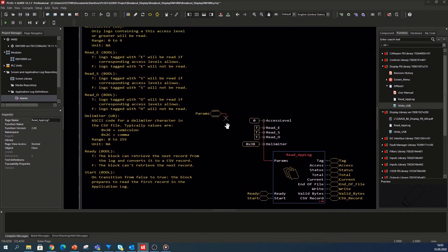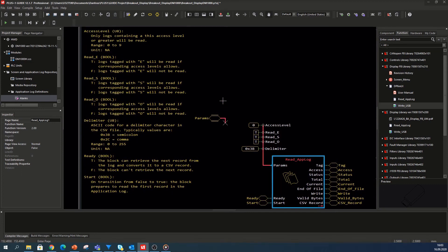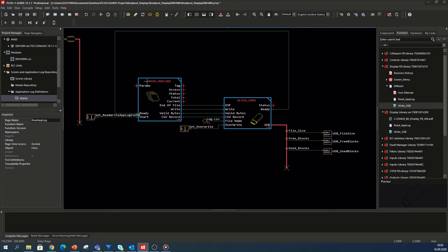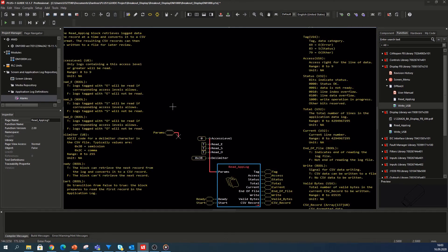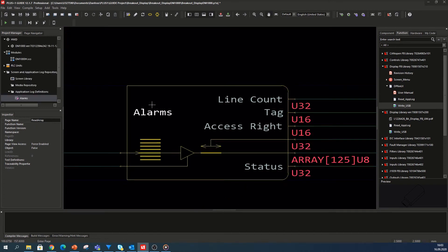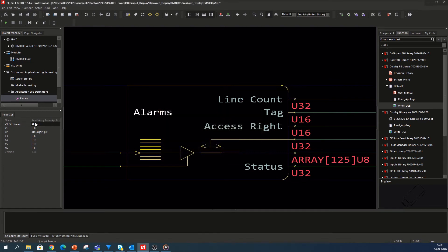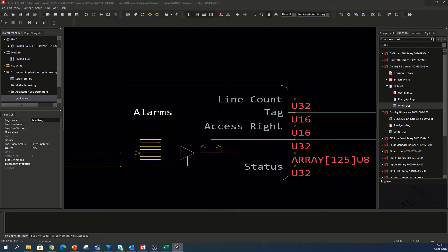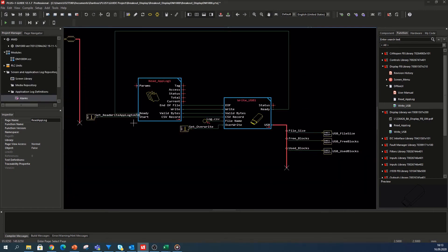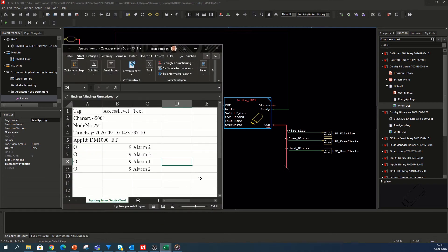At this point, almost all settings and wiring have been done, except one — the most important one: defining the file name value. To do so, you must enter the read app block page to enter the application log name. This value identifies the controller's application log file from which the read array from application log component reads records. The application log name must match exactly the application log definition name. Now all settings are done. Via the input signal start, the read app block retrieves the log data from the application log one record at a time and converts it to CSV format. These CSV records are connected to the write USB block which writes the CSV records to a file.